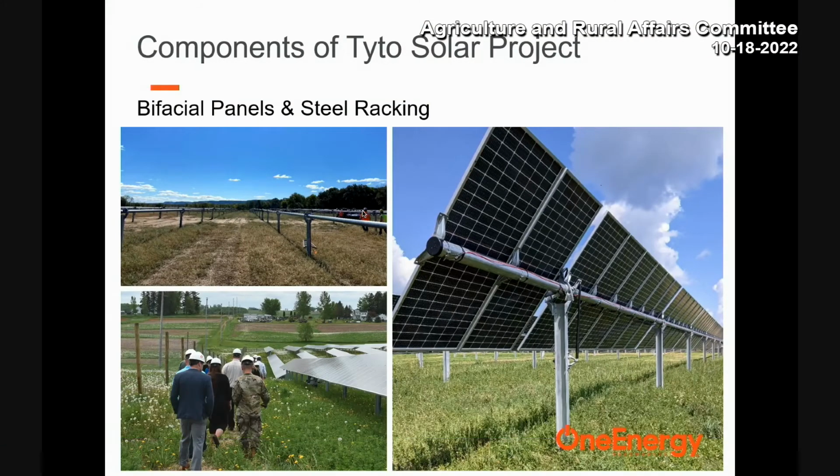Yeah, actually, this project here in the lower left is in Cashton, Wisconsin, and we built that in 2018. It was actually H&H Solar, who's right on the edge of Fitchburg and Madison, that built the project. They had a surveyor come out and stake the pile locations, and they staked two of them wrong. So they drove pilings where they weren't supposed to be.